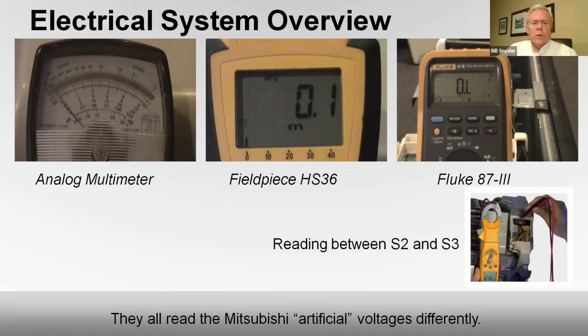In our training room, we have some analog meters, a number of these Fieldpiece type meters, and a Fluke meter. The analog meter is the easiest one to read. Now, let me just click on this and I'll show you the type of signal that you can get. That needle you see bouncing around is a typical type of signal you get between the indoor and the outdoor unit when you're reading on S2 and S3. S1 and S2 is line voltage. S2 and S3 is your communicating voltage.